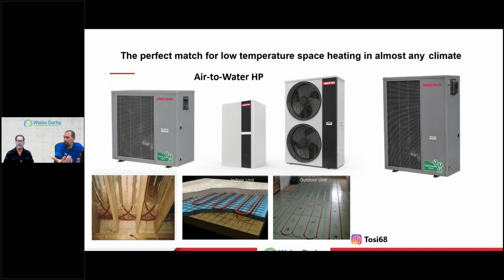But for me, when I talk to my contractors, it's always cheaper to store the BTUs than it is to make the BTUs. So if you have the space, the system volume might not need the larger buffer tanks, but you're better off still going with a larger tank and storing those BTUs instead of producing them.